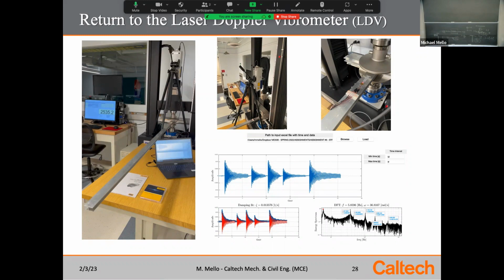If you look at what retroreflective tape is under a microscope, you'd see a field of little tiny, very, very tiny microscopic glass spheres. And it comes with an adhesive backing. So if you stick it on a surface, it scatters the light back wonderfully. An efficient scattering of the light comes right back into the vibrometer, so it really aids in getting more photons or more light back into the device. And then this is the ringing of this beam that was registered by this vibrometer. We just kept flicking it, and it would damp out. So we tell the vibrometer to record, and notice what you get sent out to you is immediately this amplitude versus time. It's already processing all this information for you.